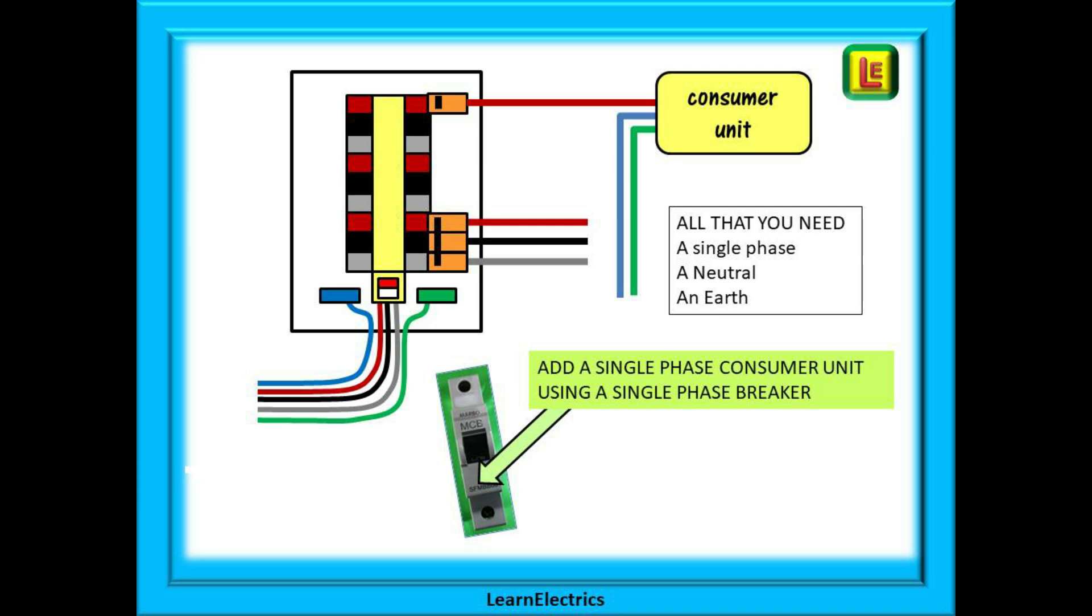Now we want to add a 230 volt single-phase consumer unit to the distribution board. Perhaps this new consumer unit is supplying an office where only single phase is required. So what do we need? A single-phase breaker to supply the new consumer unit, which in this case has been connected to the brown phase. A feed from the single-phase with the appropriate size cable for the load. A neutral and an earth. That is it. Think of a three-pin plug. What has a three-pin plug got? A single-phase, a neutral and an earth.